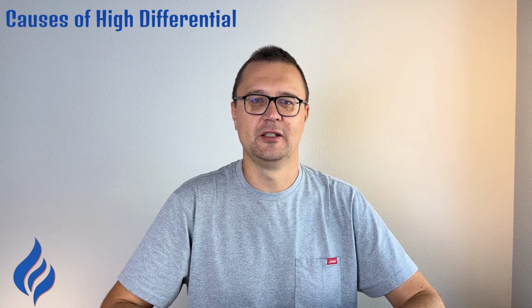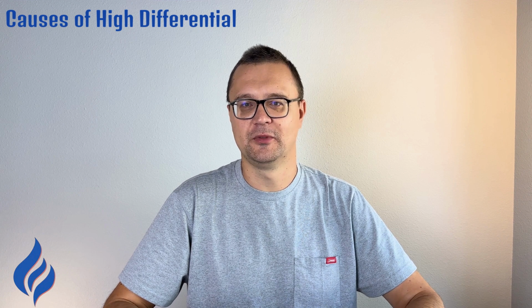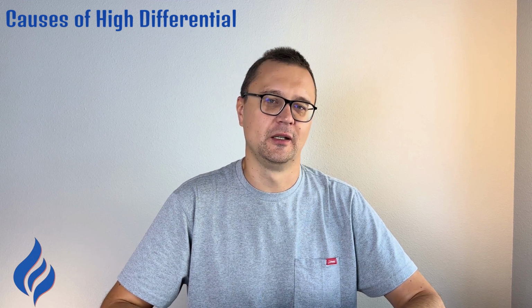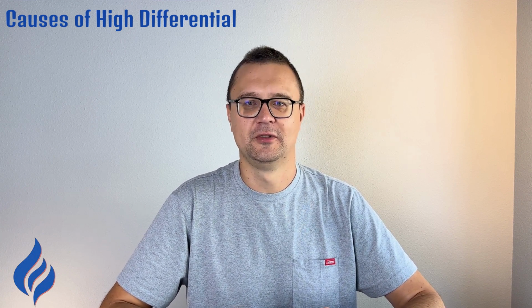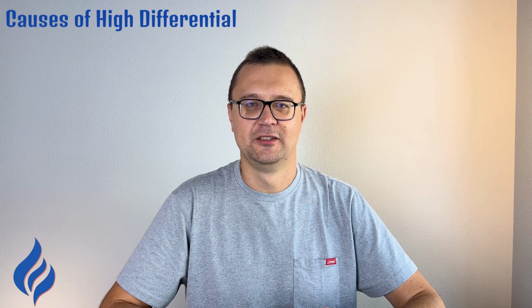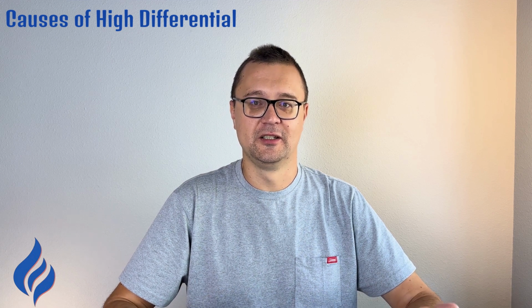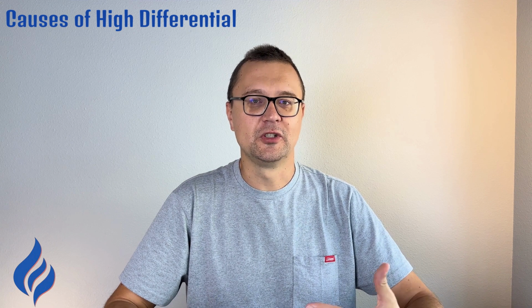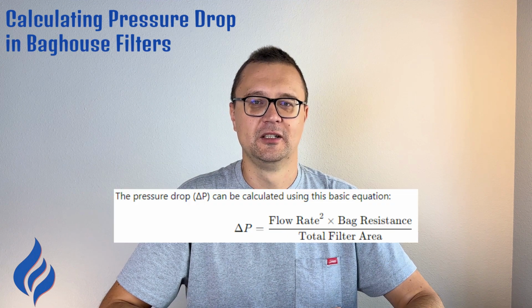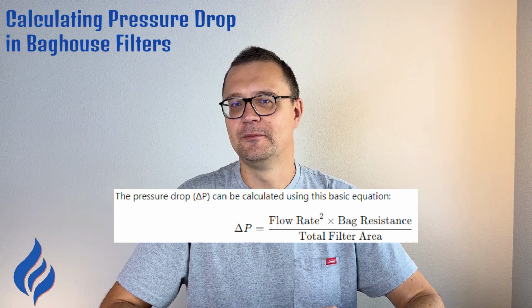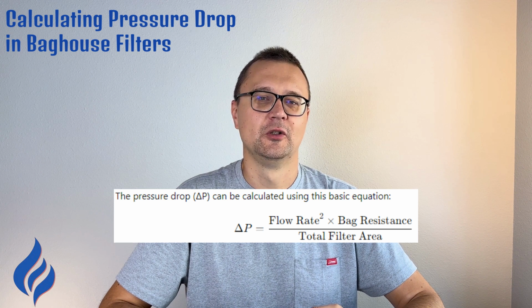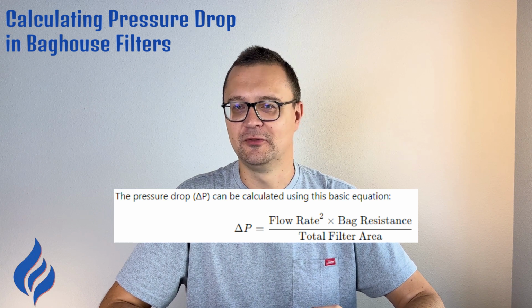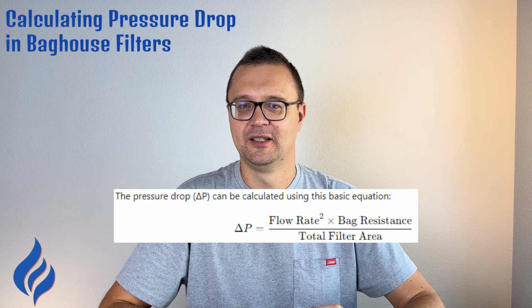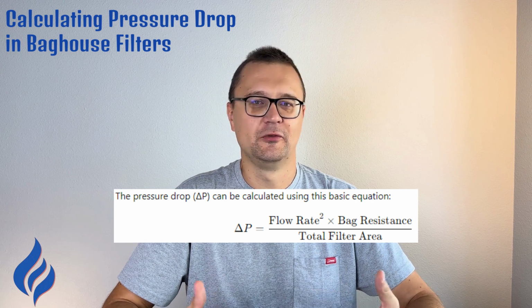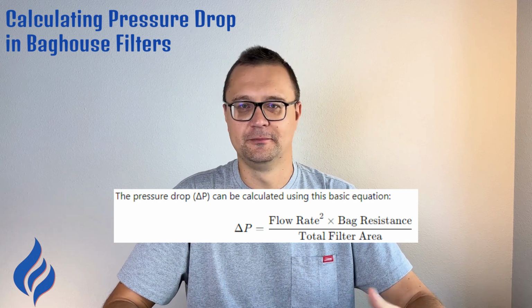Design flaws or maintenance issues. Sometimes the cause is poor system design, including narrow ducts or undersized fans. In other cases, insufficient maintenance, like neglecting to clean out dust buildup, can worsen the issue. Calculating pressure drop in baghouse filters. Pressure drop is a vital measure of how well your baghouse filter system is performing. While this might sound complex, here's a simplified version of how to calculate it.